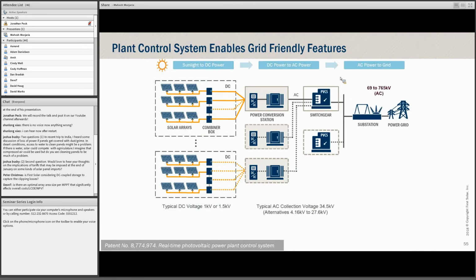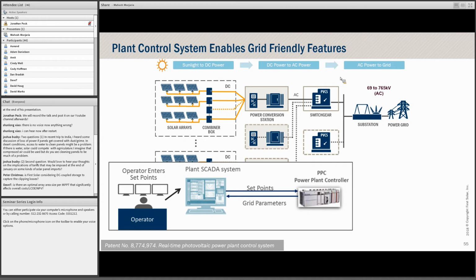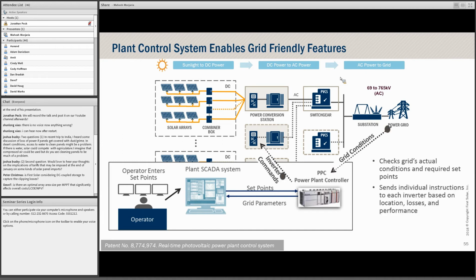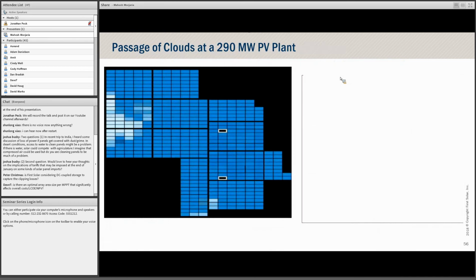So we take the power plant, and on top of that we layer a power plant controller with a SCADA system. This controller monitors the grid conditions and commands the inverters - the active elements, of which there could be hundreds - so that the whole system works as one harmonious unit. It's almost like an orchestra conductor, ensuring the total output of the plant is what we desire. This is a closed loop system running at about 100 milliseconds, so pretty fast, which lets it handle a lot of things.